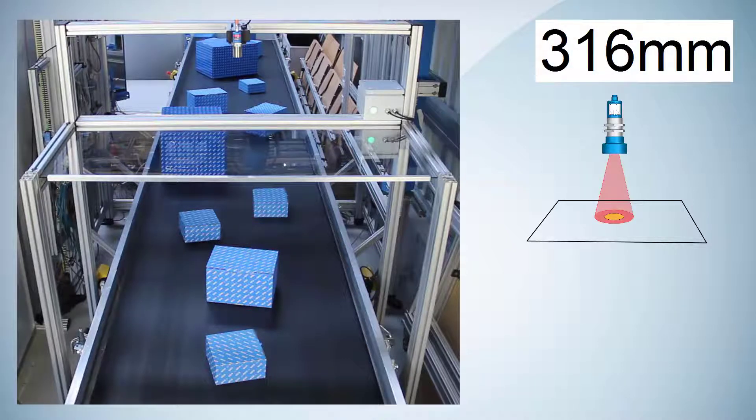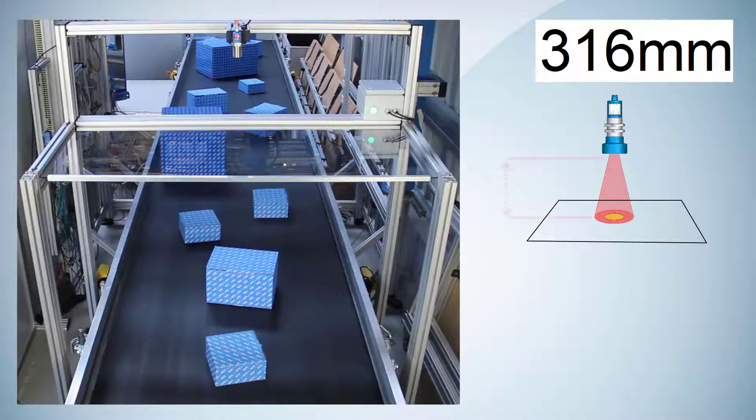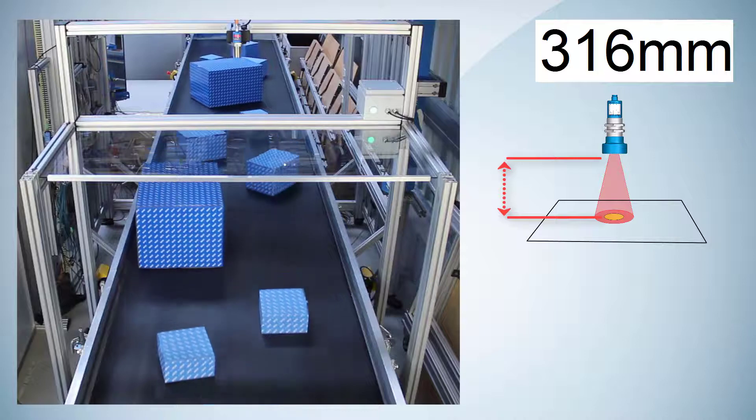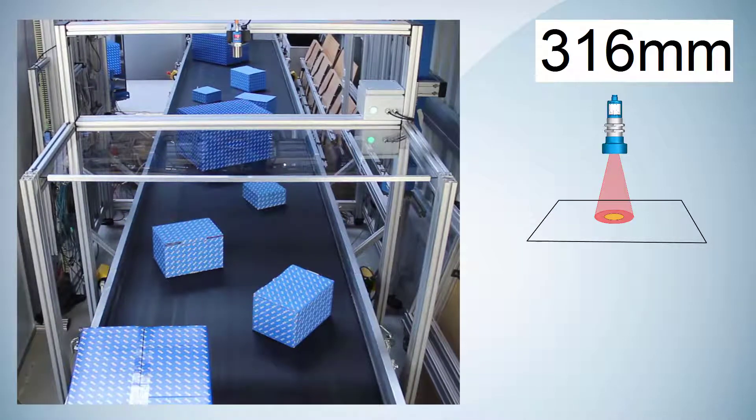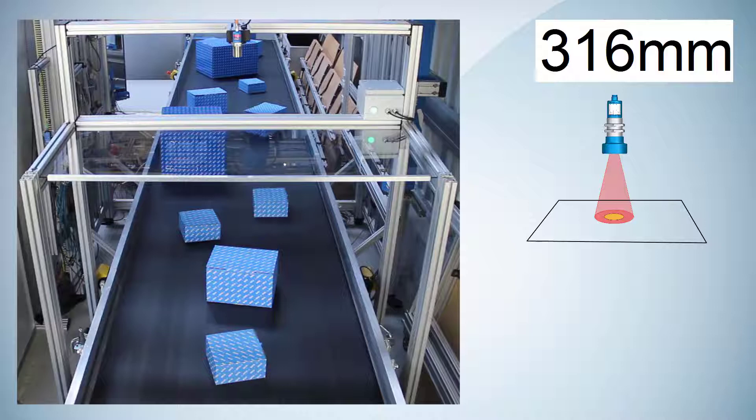When we start the sensor, the display shows a measurement value of 316 millimeters. This is the distance between the sensor and the acrylic glass. Currently in the default settings of the sensor, the sound cone is too wide to look through the hole in the glass.